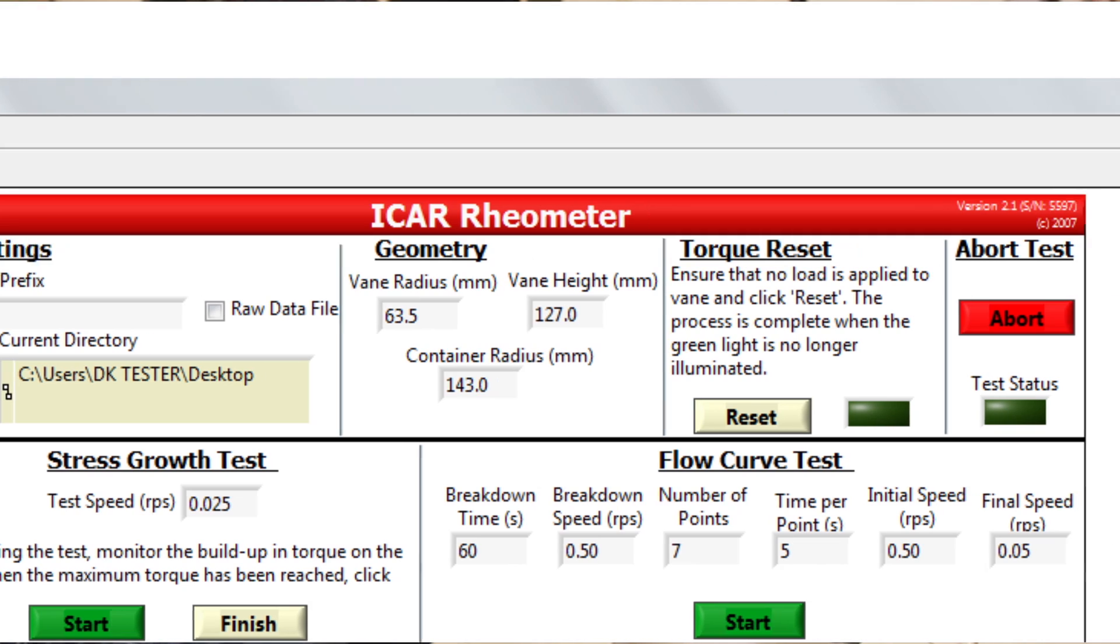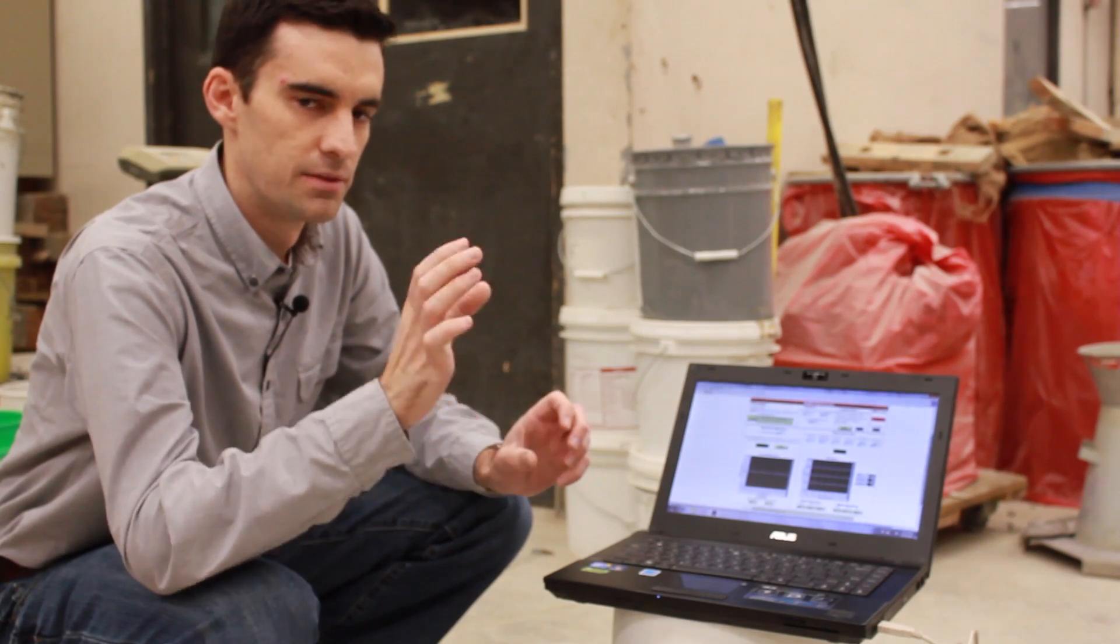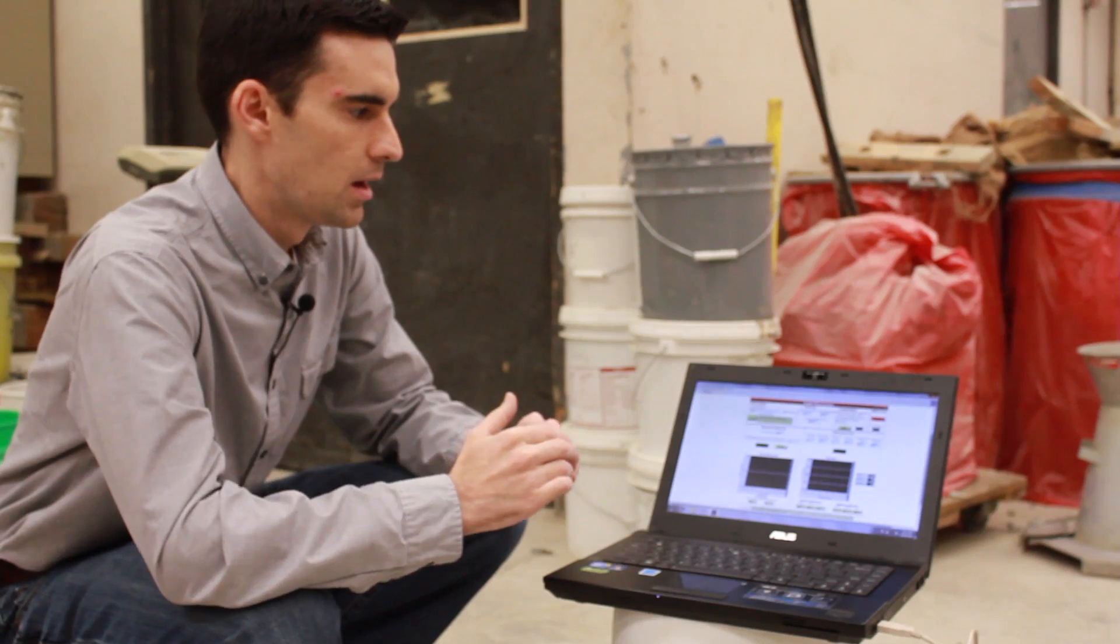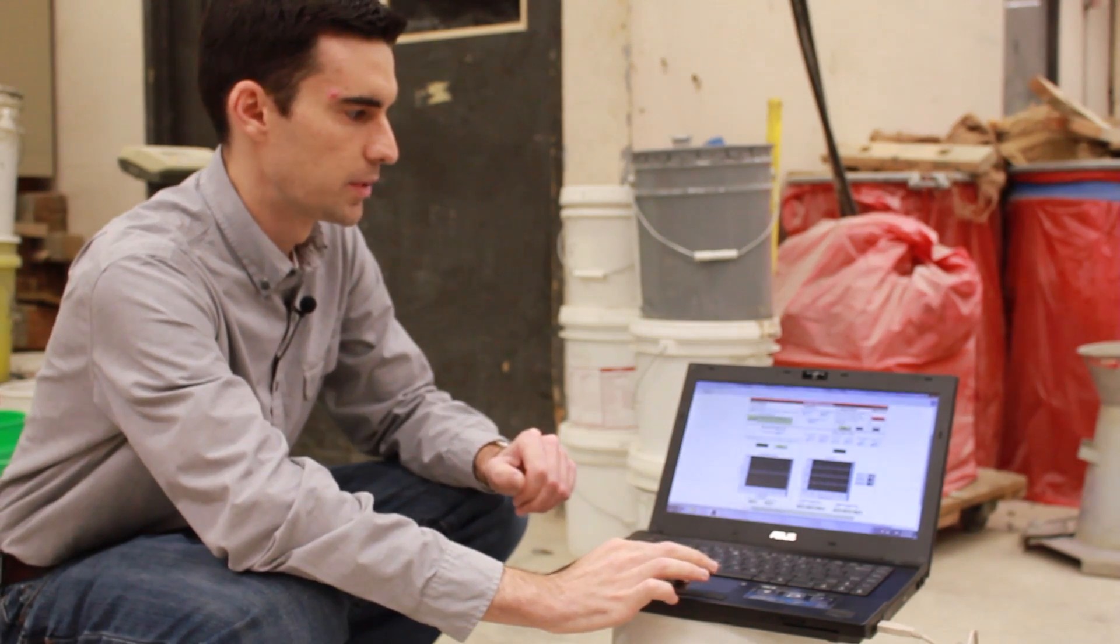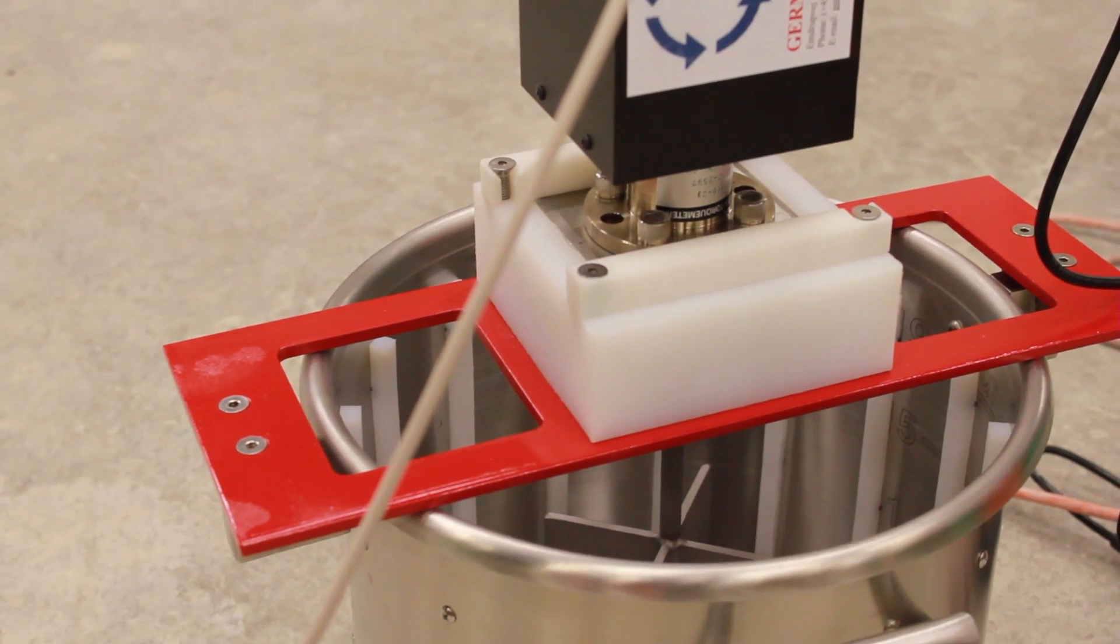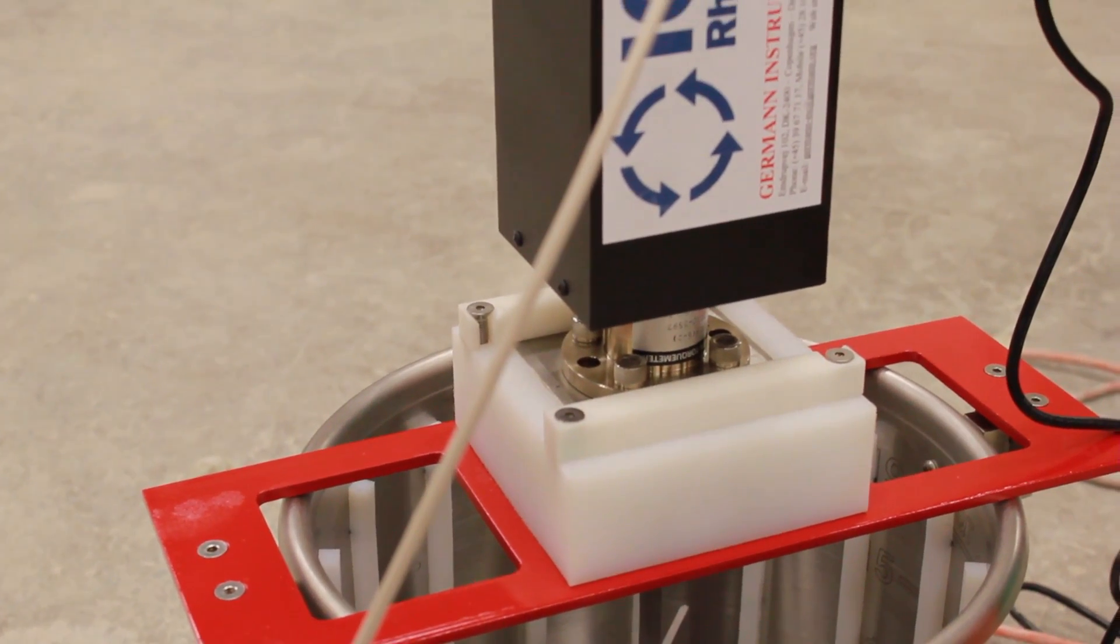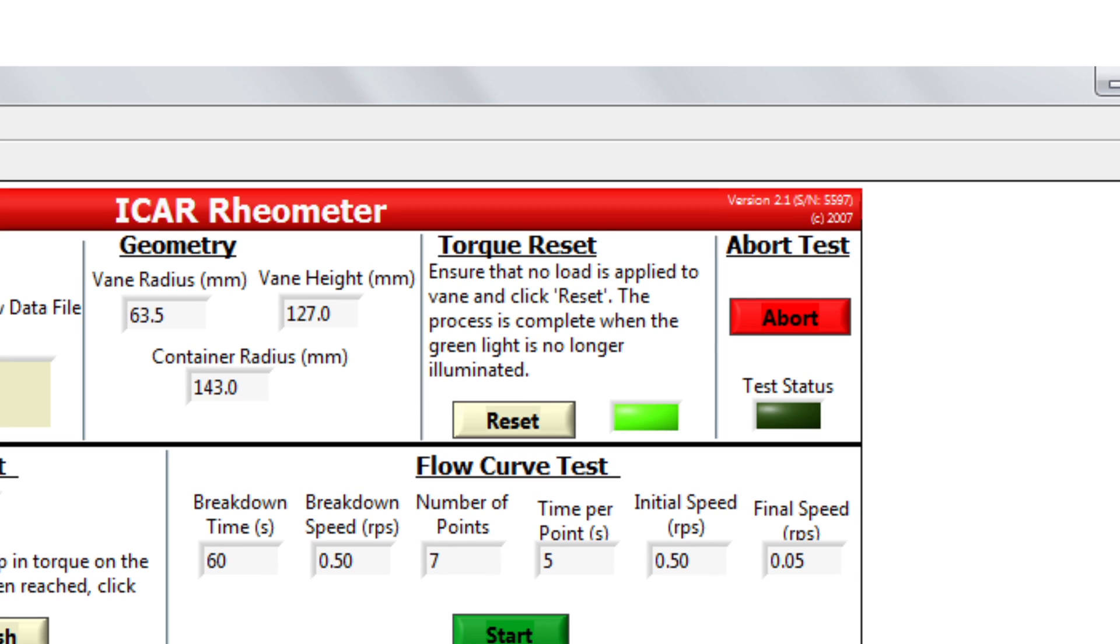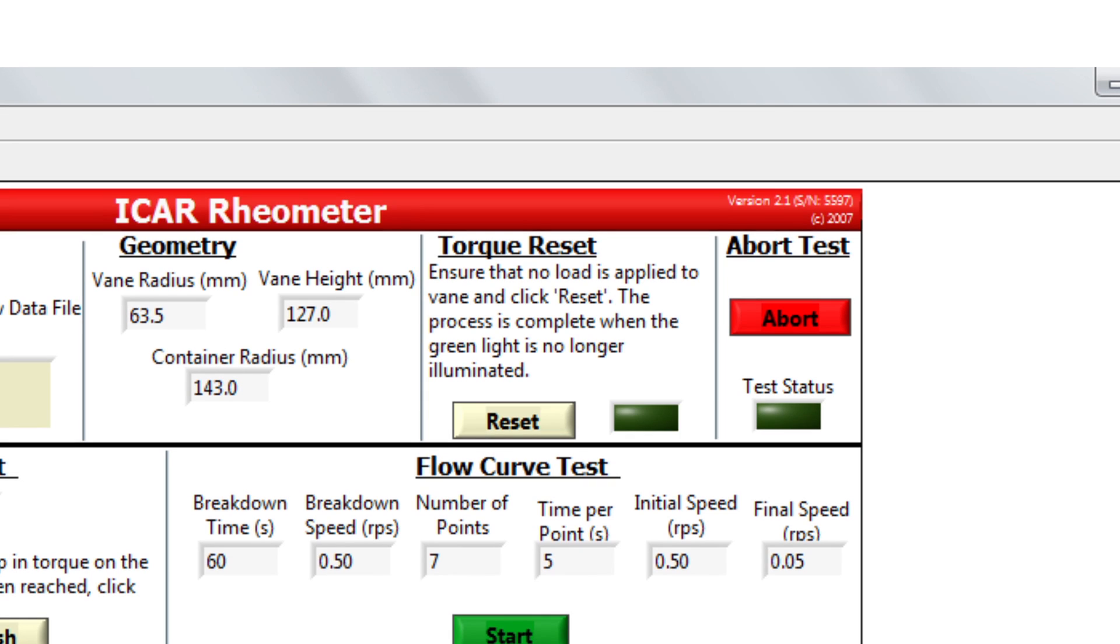The next thing we do is we need to zero out the torque. So that when there's zero torque acting on the vane, the rheometer is actually reading zero torque. We want to do this at the beginning of the day and then between every test. We have our rheometer set up with no material touching the vane. So we're confident that there is zero torque acting on the vane. We then press reset. We watch for that light to illuminate. When the green light turns off, we reset our torque.